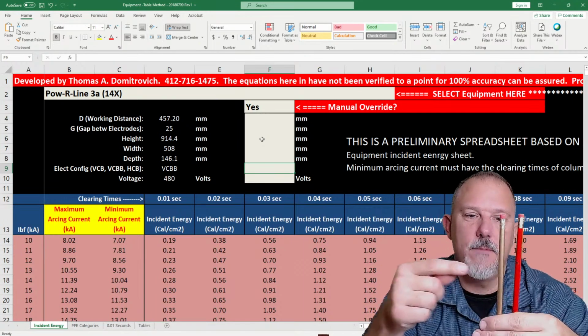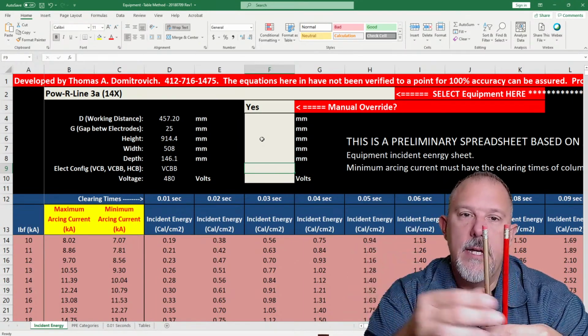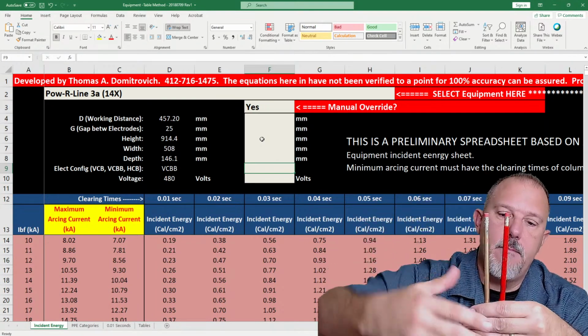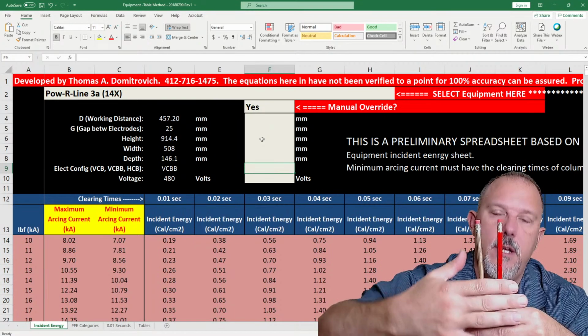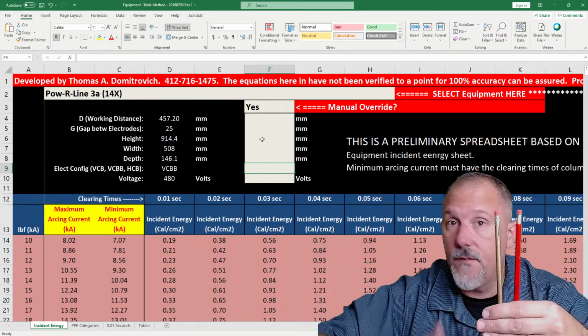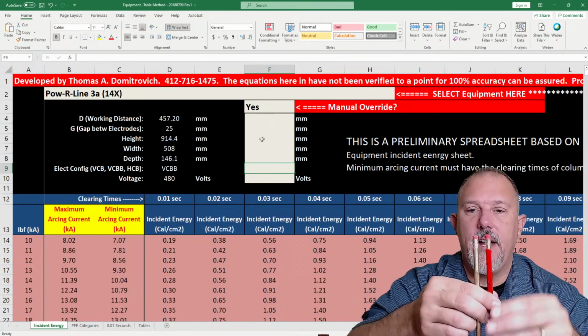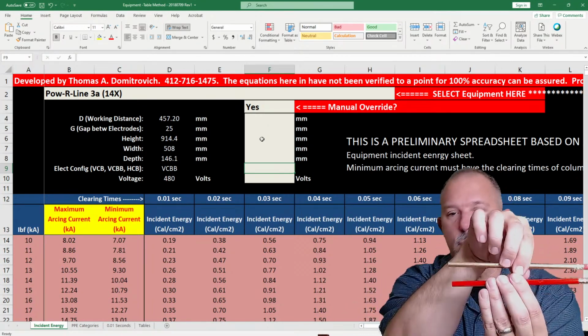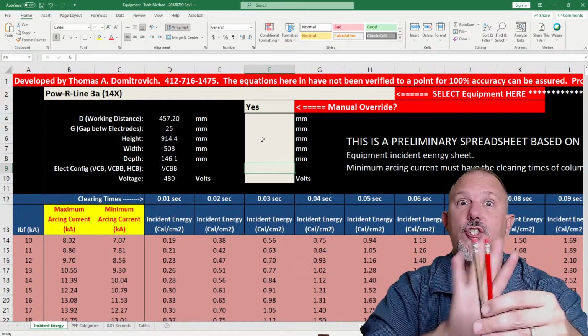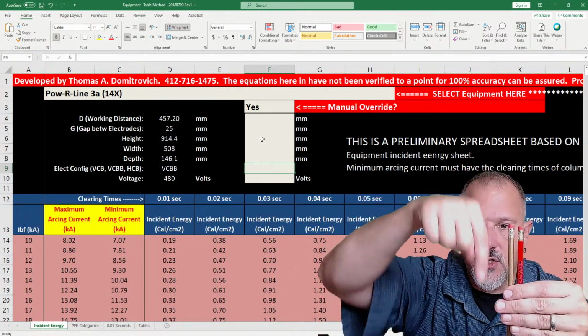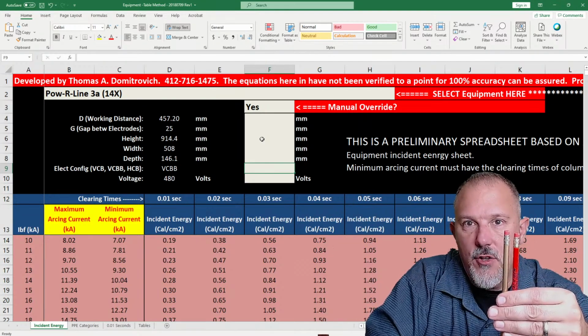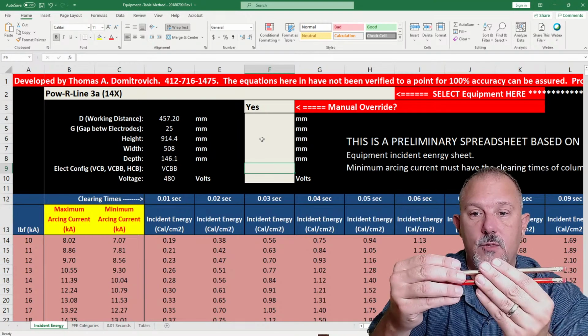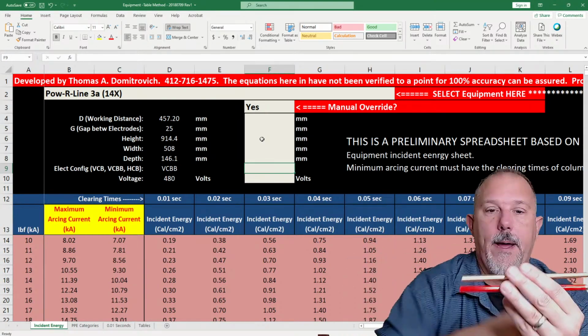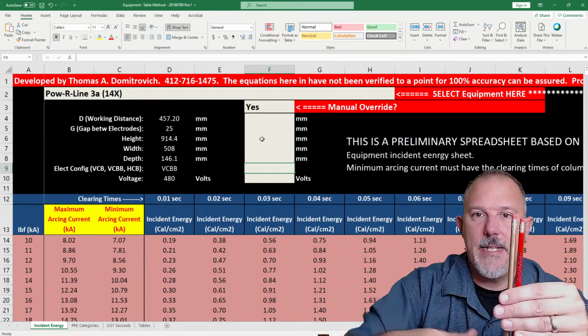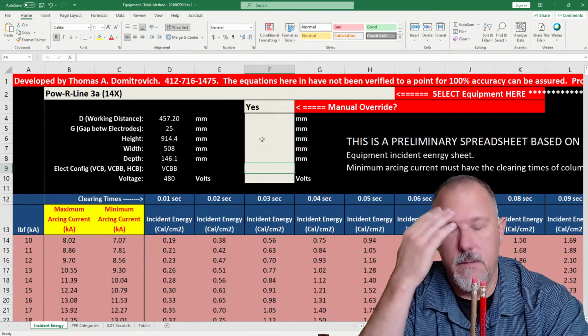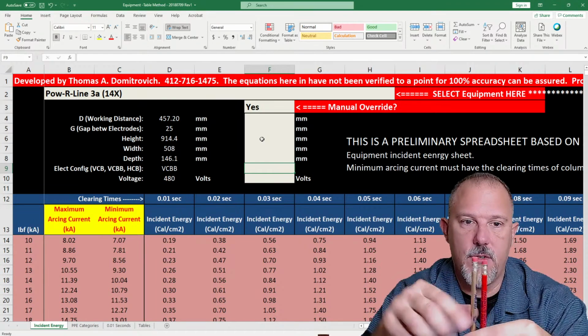So what do we know about the arc? If this is my main and my fault is here on the bus, the arc will always flow away from the source. So if I'm looking at a bus and a panel board this way or this way, doesn't matter. I'm looking at the major portion of the copper. My arcing currents will flow down. Or if my main is down here in the bottom, it will flow up. Or if it's this way and my main is over here, it will flow that way. But it flows up and down, horizontally, vertically, left and right.